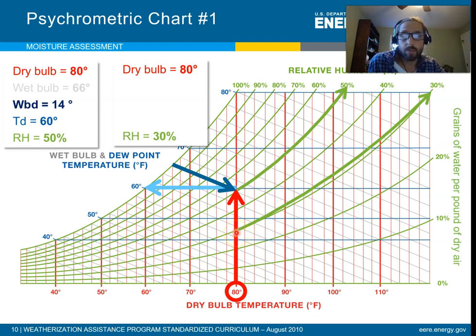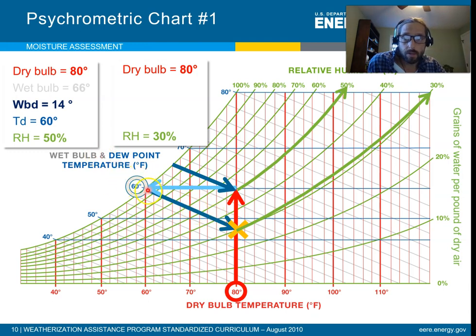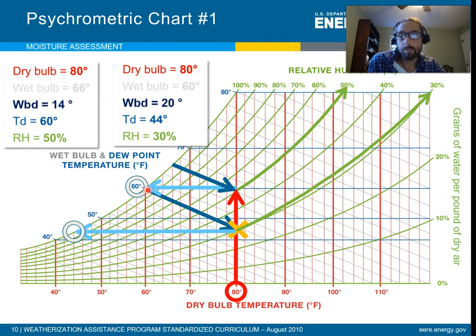If you follow it up along the gray wet bulb lines, the wet bulb is about 60 degrees. The dew point is straight across to the left, so it's about 44 degrees. Our wet bulb depression is 20.